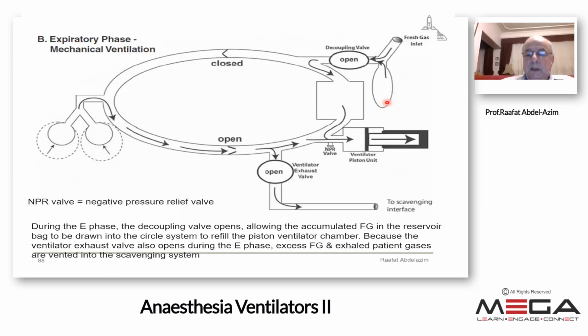During expiration, the decoupling valve will open, allowing gas from the fresh gas flow and from the reservoir bag to come into the circuit, but not in the direction of the patient, but in the direction of the piston, because during expiration, the piston will move in the other direction, extracting what is coming from the patient's lung. So the expired volume will come into the expiratory limb, into the piston, and it will fill the piston again according to the preset tidal volume.